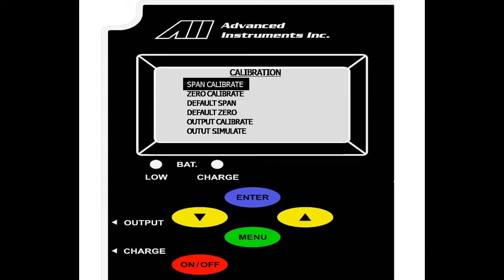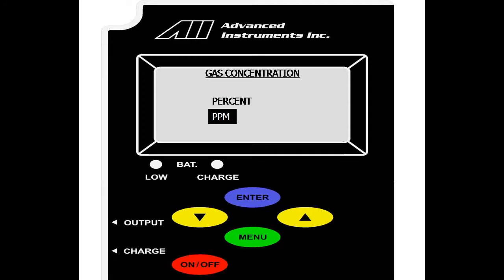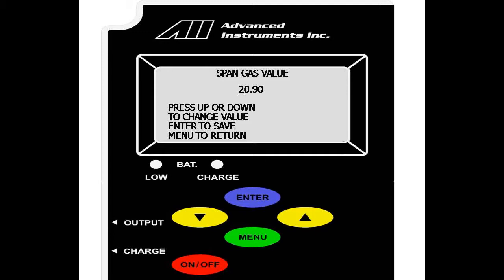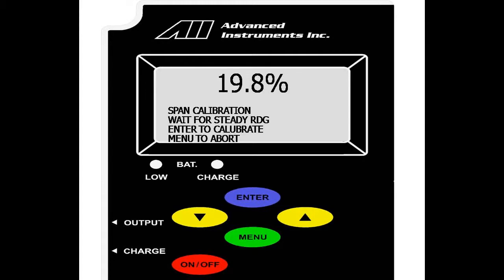We scroll up to span calibrate and select enter. Since this is an air calibration, we will hit the percent. However, if you are doing a span calibration with certified span gas, you will scroll down to PPM. We select enter on percent and as a default value, we have 20.9, fractional percent of oxygen in dry air. If we were to change this, we select up or down to change the value and enter to move over. Once we have set the value, we are taken to the live reading screen.